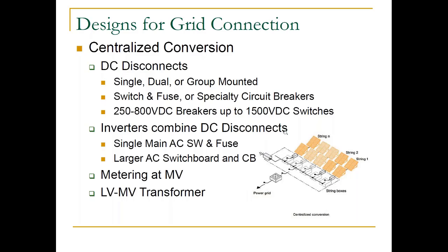Similar things here. Oftentimes there'll be metering up at the medium voltage level. It usually means they're trying to keep the AC switchboard a little bit smaller footprint. In these installations, you often see that the DC disconnects or the group mount disconnects are maybe a wall mount application, or if it's on a skid, they'll have a little bit more compact installation on the DC boards.